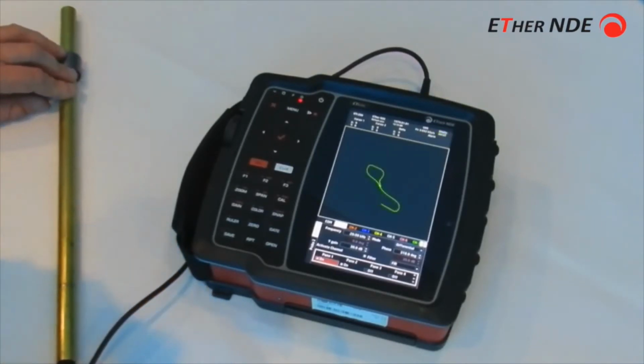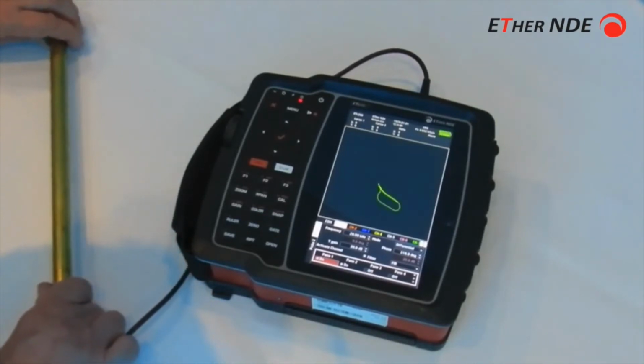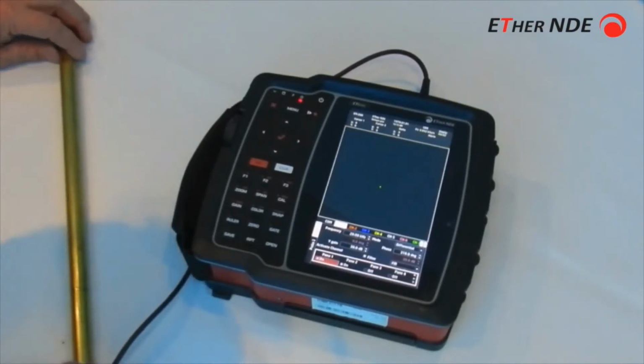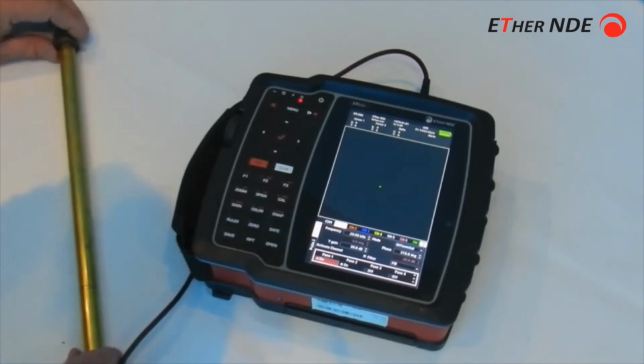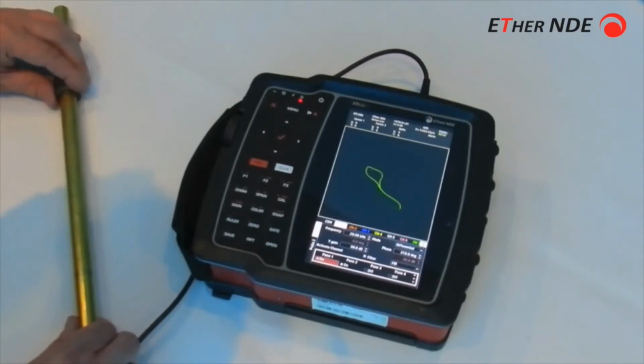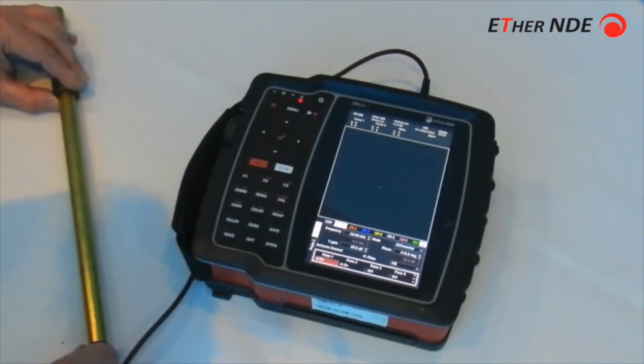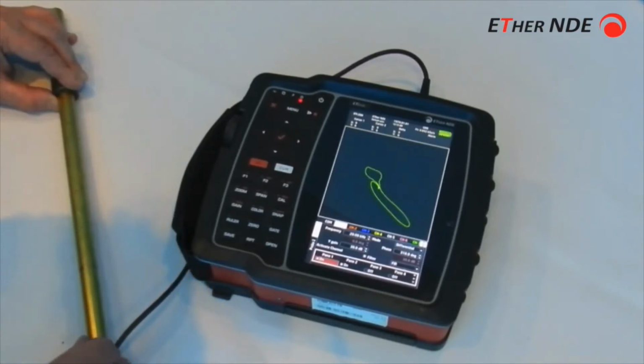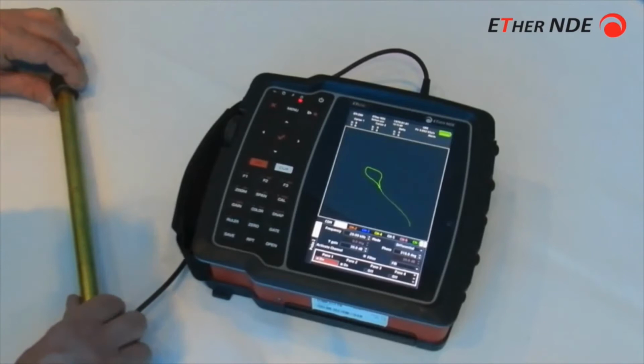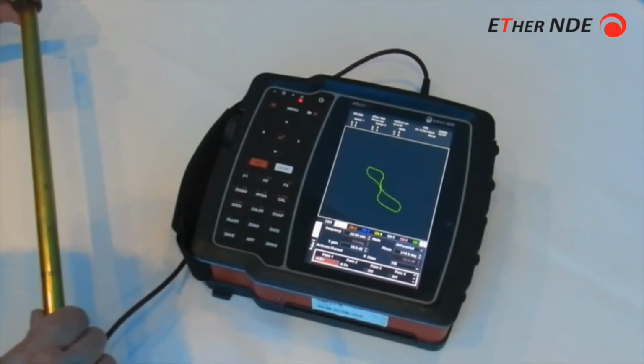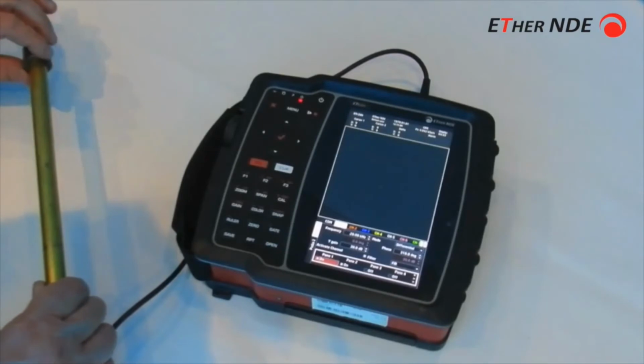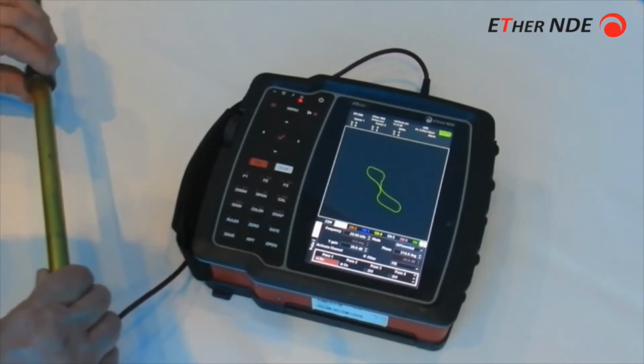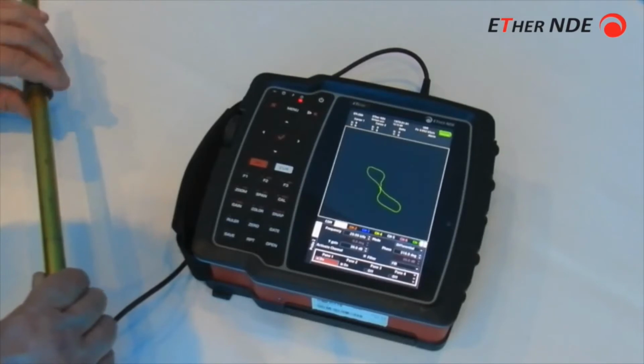There is a support plate signal caused by the ferrous support plates along the length of the tube, and they give this sort of more like an open figure of 8 signal, which is quite different in characteristics to the defect. But if you're looking at and analysing, this can sometimes be difficult, particularly if you have the defect by the hole. Now you have a strange loopy signal caused by both together, and one of the ideas is to use dual frequency to remove the effect. And we'll demonstrate this in a second.